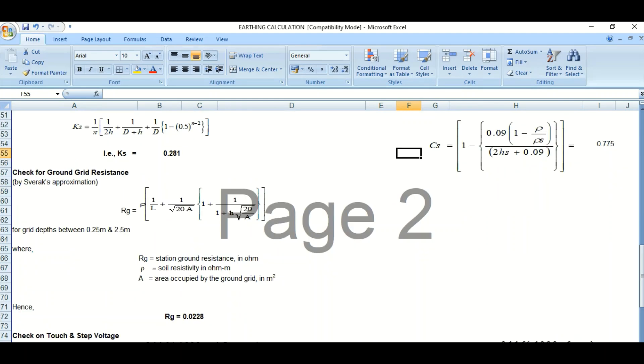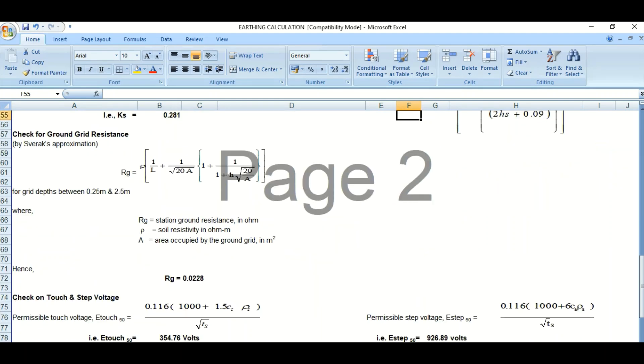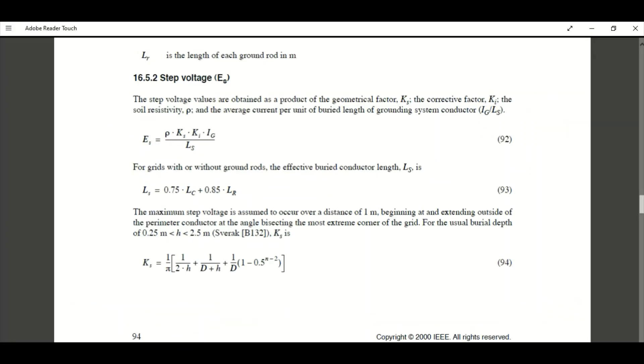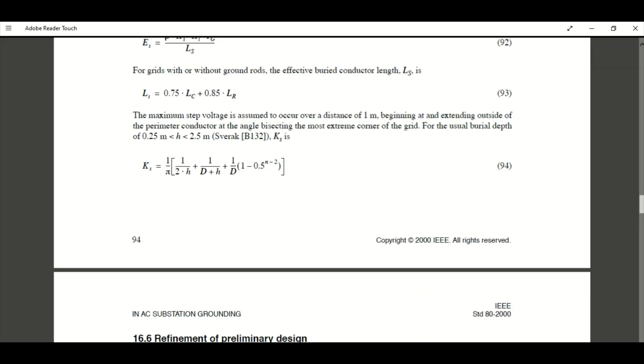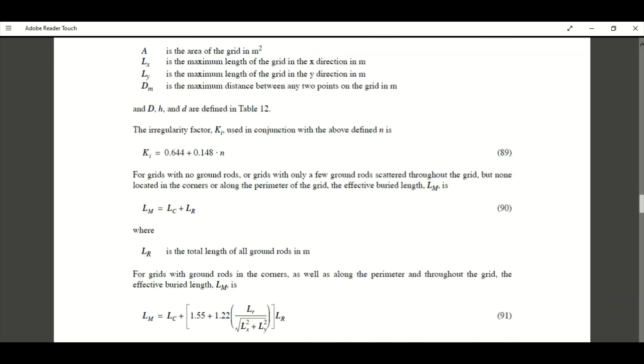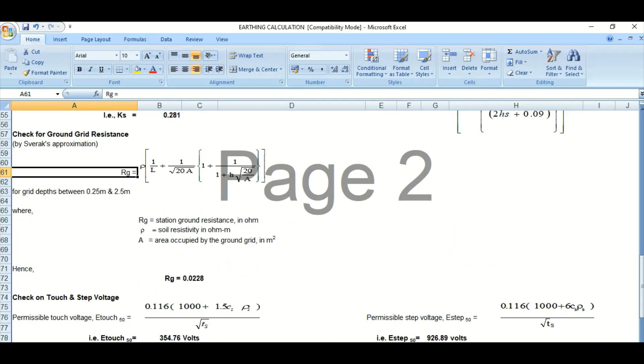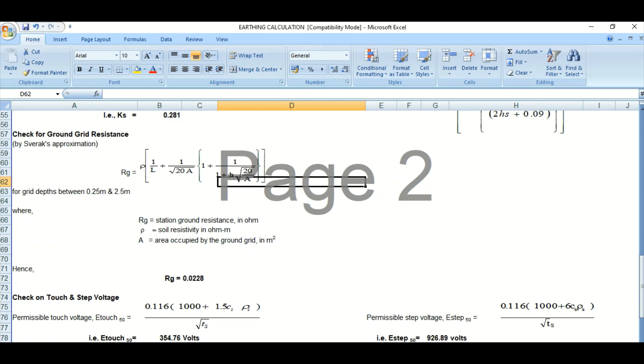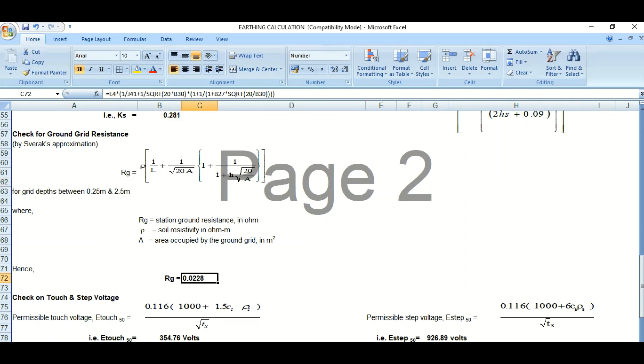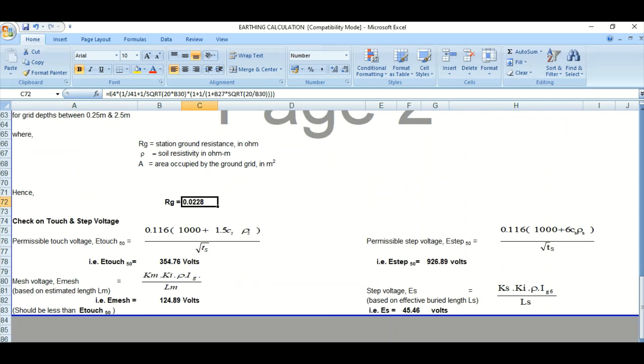Next we need to check the ground grid resistance. Using the formula from IEEE 80, we have calculated the value of Rg as 0.0228 ohms. Now the main thing is coming — to calculate the touch and step voltages.